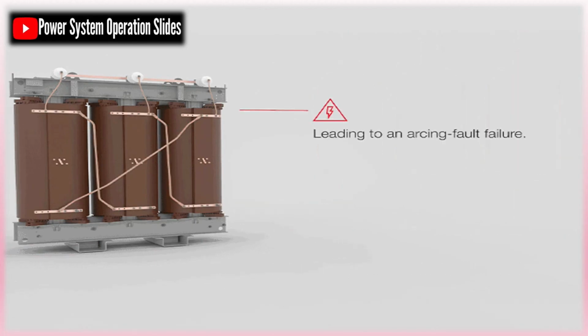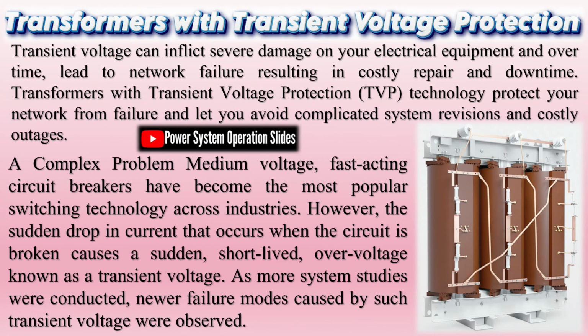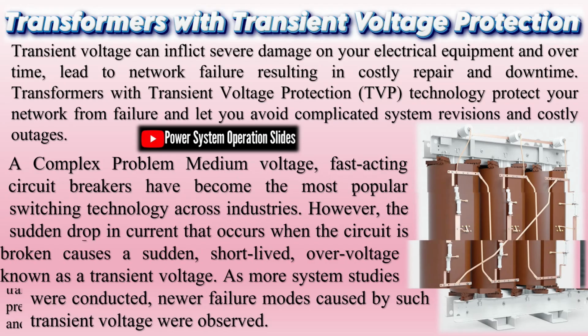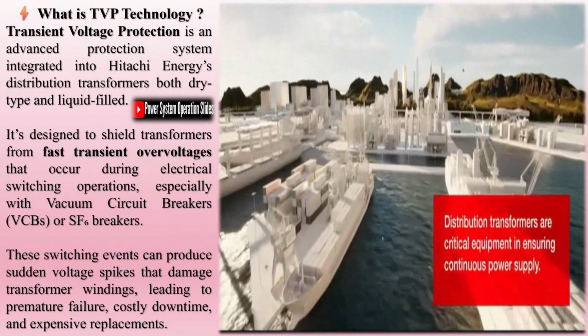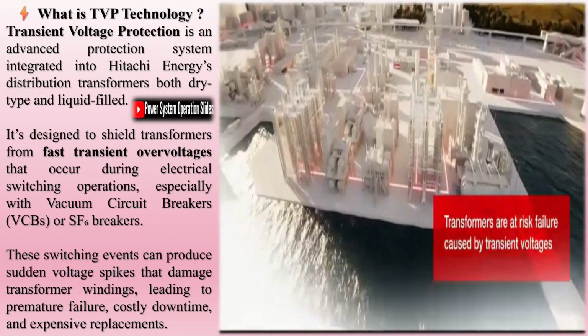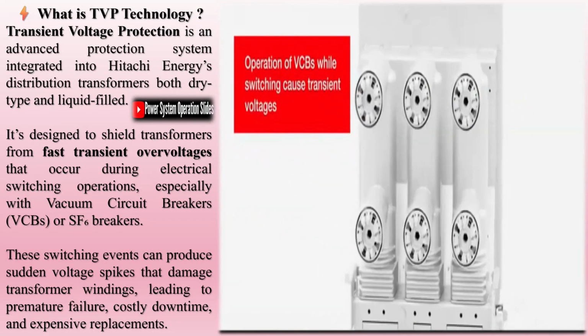dissipating excess energy. Transient voltage can inflict severe damage on your electrical equipment and, over time, lead to network failure resulting in costly repair and downtime. Transformers with transient voltage protection technology protect your network from failure and let you avoid complicated system revisions and costly outages. A complex problem: medium voltage, fast-acting circuit breakers have become the most popular switching technology across industries.